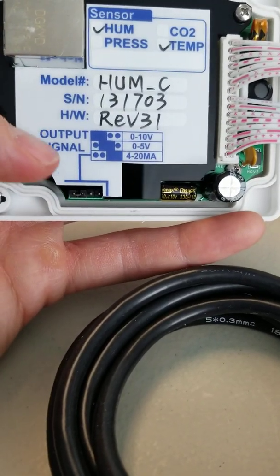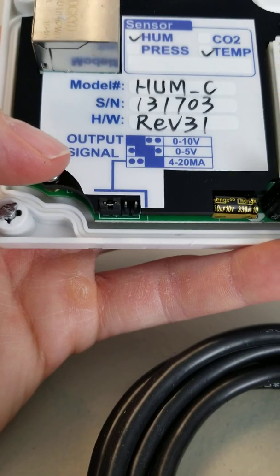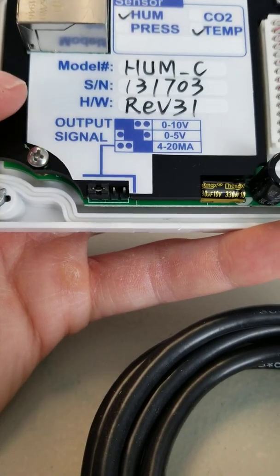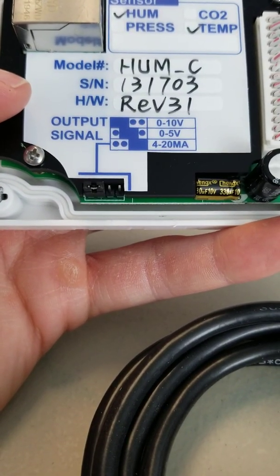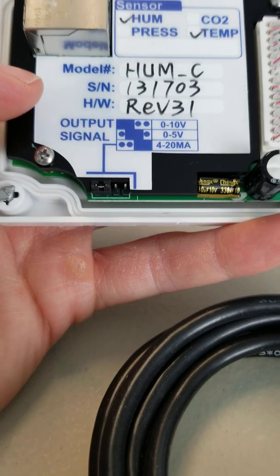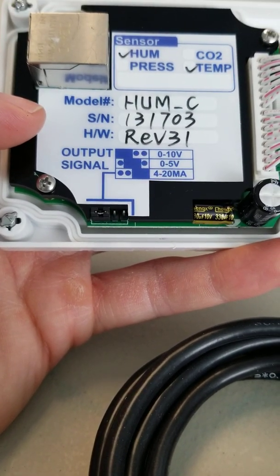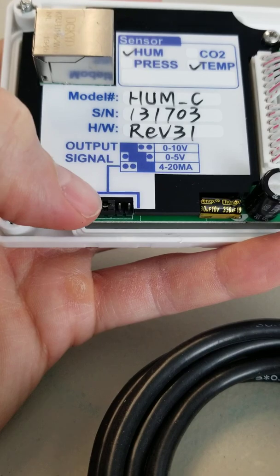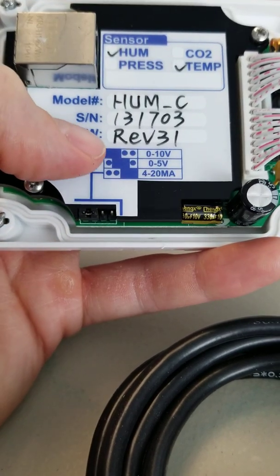Down here there's a little jumper, and depending on how you set that jumper, the analog output will output 0 to 10 volts DC, 0 to 5 volts DC, or 4 to 20 milliamps. Right now in the left setting, on the two left pins, you can see it's 0 to 10 volts.